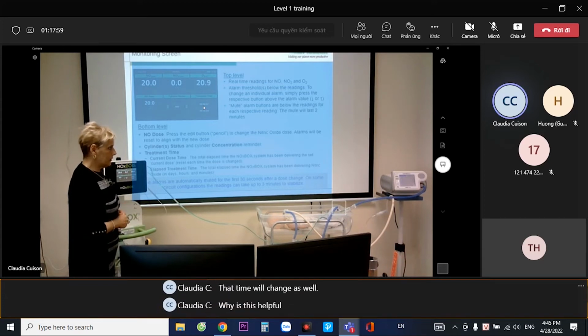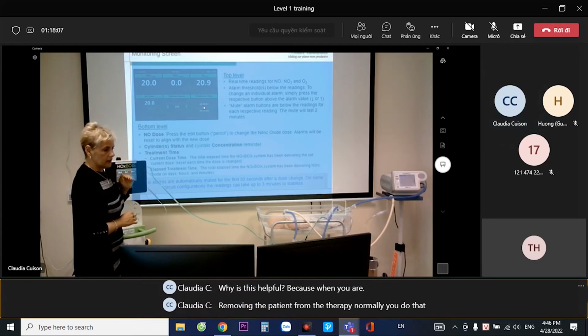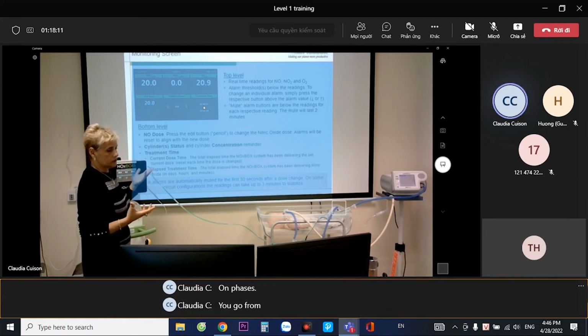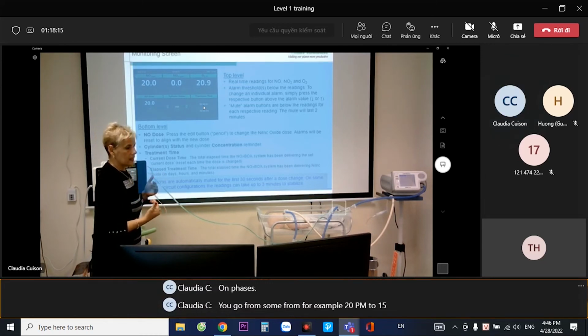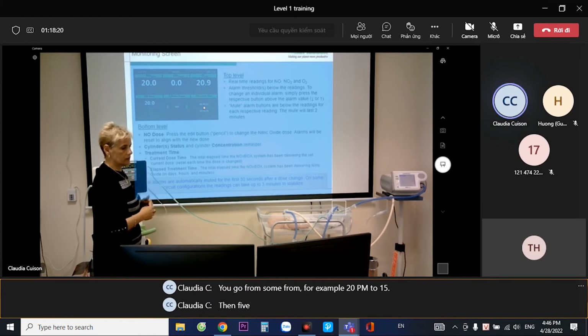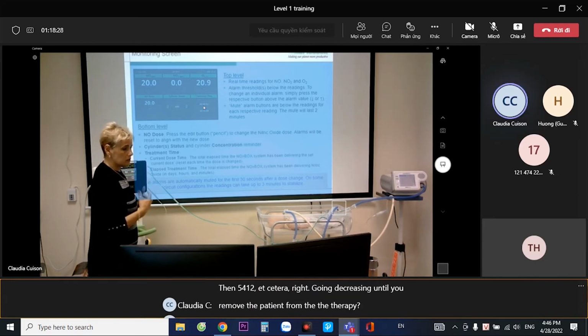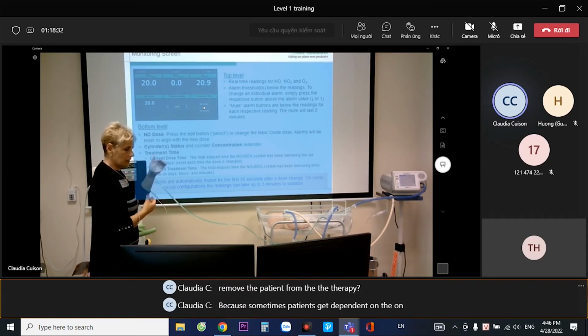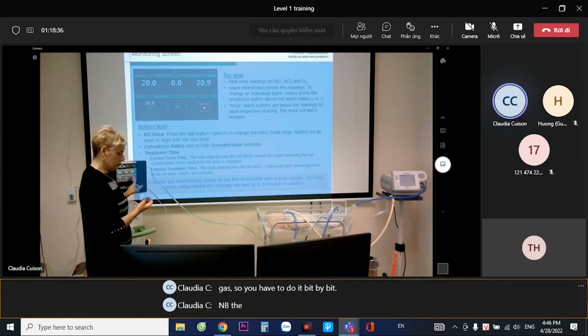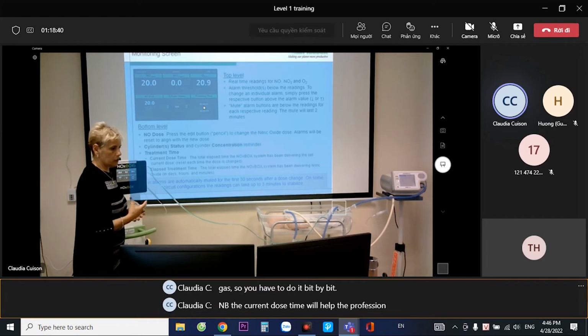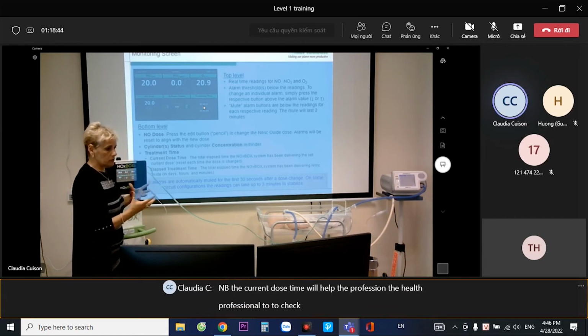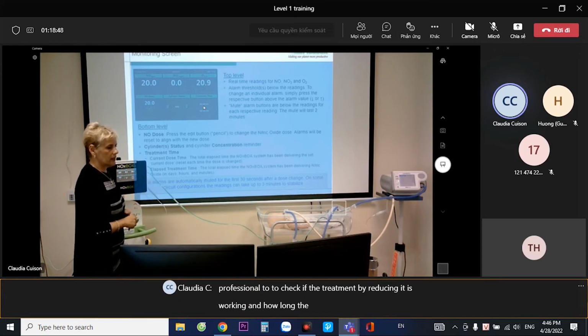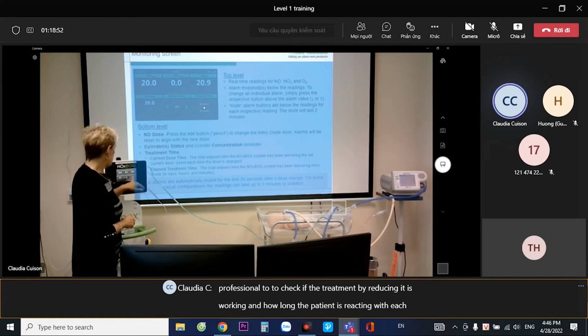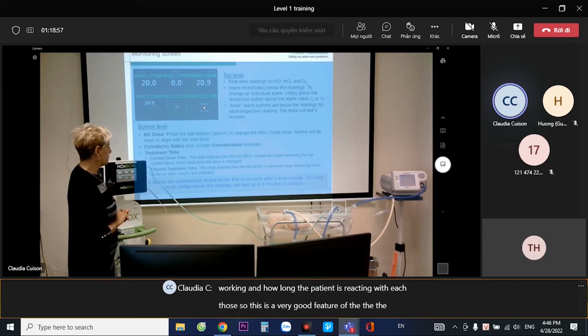Why is this helpful? Because when you are removing the patient from the therapy, normally you do that in phases. You go from, for example, 20 ppm to 15, 10, 5, 4, 2, 1, etc. Right? Decreasing until you remove the patient from the therapy, because sometimes patients get dependent on the gas, so you have to do it bit by bit. And the current dose time will help the health professional to check if the treatment by reducing it is working and how long the patient is reacting with each dose. So this is a very good feature of the unit.